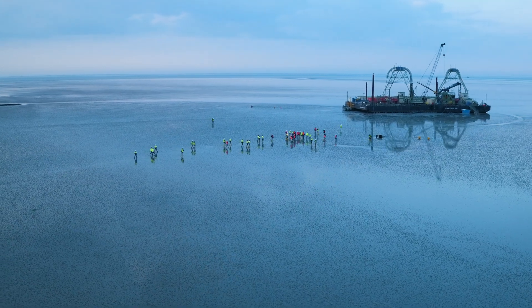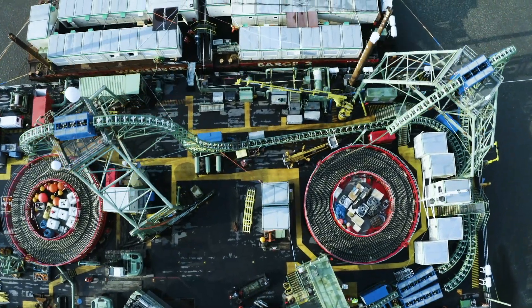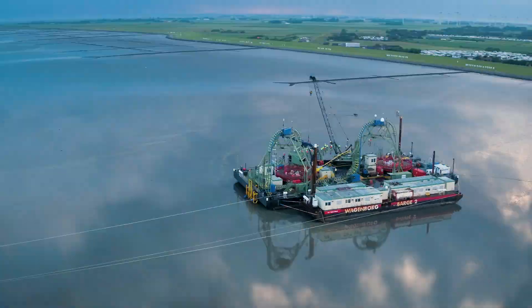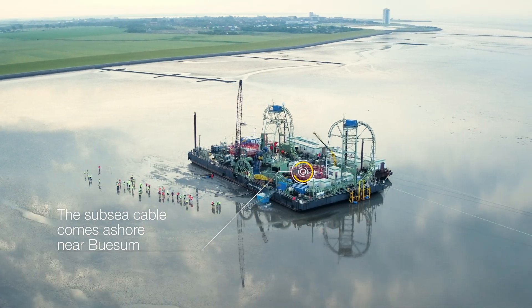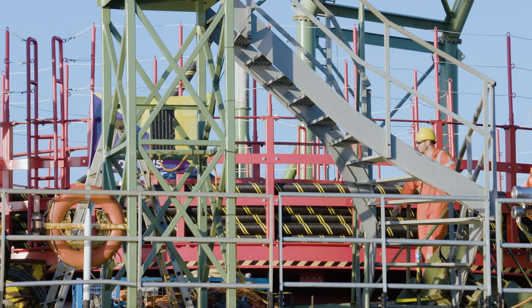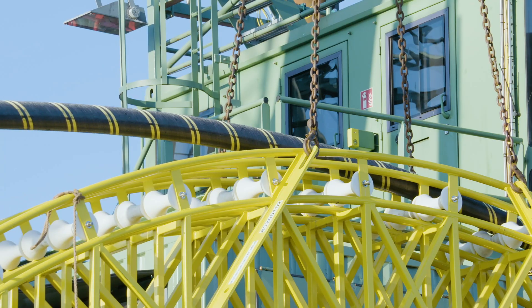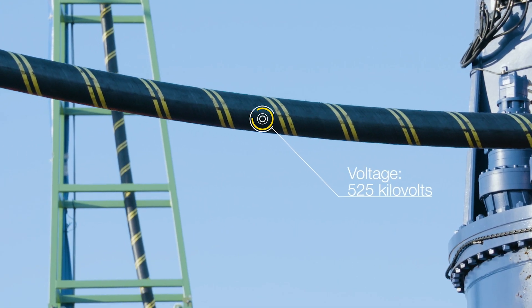Nordlink — the green link for the exchange of Norwegian hydropower and German wind power. After traveling almost 600 kilometers from Norway under the North Sea, the cable will come ashore in Schleswig-Holstein, Germany. The electricity must be transported over this distance with the lowest possible losses. TenneT therefore utilizes high voltage direct current transmission with a voltage of 525 kilovolts.